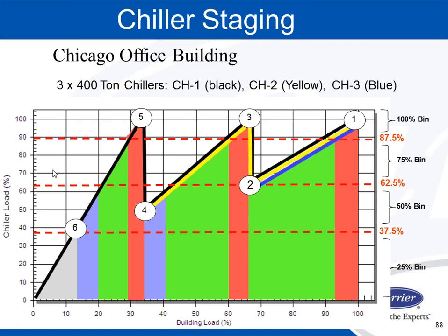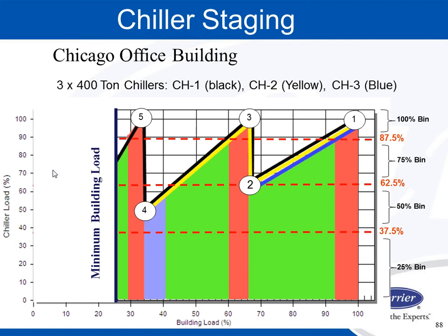Okay, now we live in Chicago, and we know that the majority of the time we operate with air side economizer when we can. So with air side economizer, that would be the line in blue, everything shaded would be the minimum building load, which basically eliminates altogether the 25% load point. Now, if you remember when we were looking at the 25% load point, IPLV had 12% weighting factor on the 25% load point.